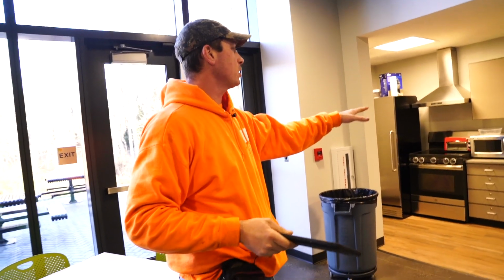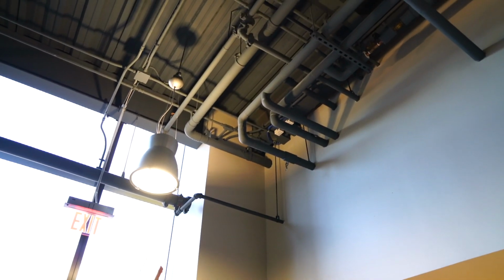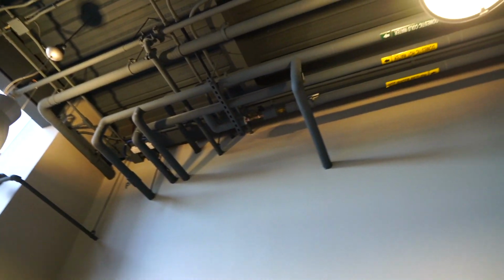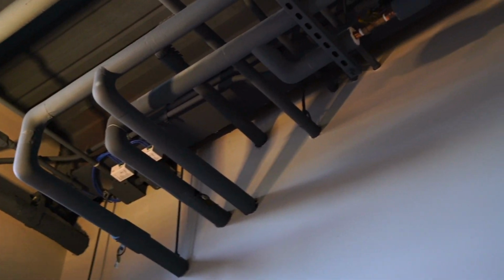So for the sinks here, water feeding the ice maker for the refrigerator. We have all our isolation valves up here, hot, colds. You can see the hot water return line right here. We have our balancing valve, check valve, another isolation valve. All our valves have tags on them. You guys have tag numbers that tell you what shuts off what.